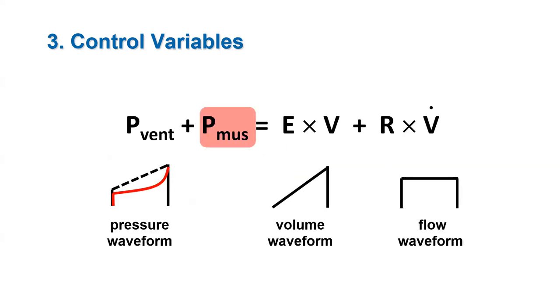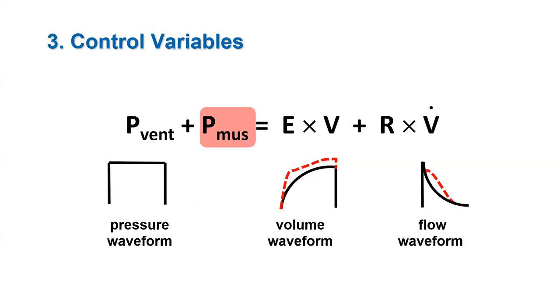The equation of motion is introduced as the theoretical basis for waveform interpretation. It explains the effects of changes in mechanics on the pressure, volume, and flow waveforms. Here we see the effects of inspiratory effort on the pressure waveform during volume control. In contrast, these are the effects of inspiratory effort during pressure control ventilation.